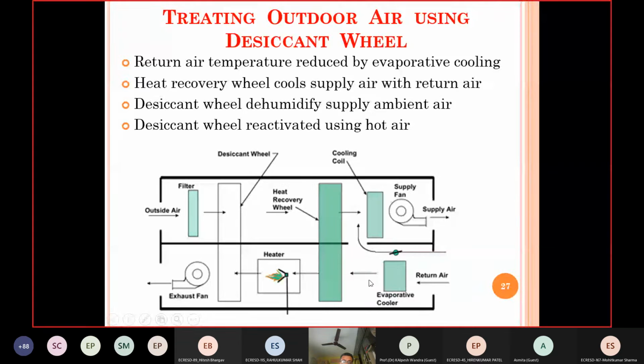So this air is having lower temperature, while the outdoor air is having higher temperature. Right? If you just consider some numbers, the return air, let's say, is at 27 degrees Celsius and 50% RH, while the outside condition could be, let's say, 40 degrees Celsius and 20% RH or something. Right? So here you are cooling it, okay, and now it has more potential for cooling. So you use the heat recovery wheel.